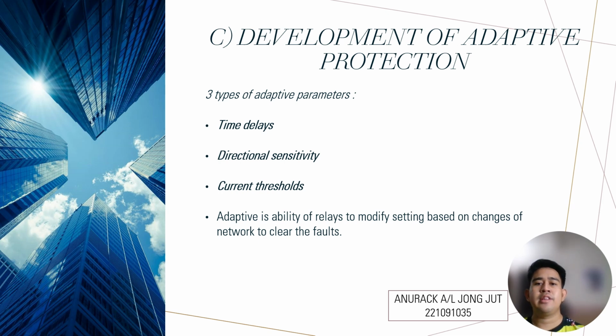So what is adaptive protection? It means the ability of the relay to modify settings based on the changes of the network to clear the faults that occur. There are three types of adaptive parameters. First is time delays, second is directional sensitivity, and third is the current thresholds.